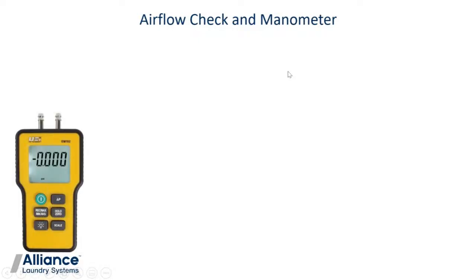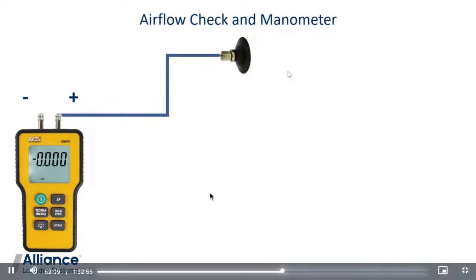So we just want to take that a step further with a tool. We showed it in there, called a manometer. This is a little bit different one, but a manometer can read vacuum or negative pressure, or static pressure. There's positive pressure, depending on which port you use. Obviously, when we're looking at vent work, we connect to the positive side to read, and we need a suction cup. Do you guys want to see this, or can I just skip through this? Are you guys familiar with a manometer? I'll skip through it. We'll go back if you want it.